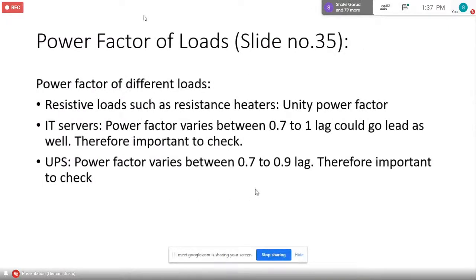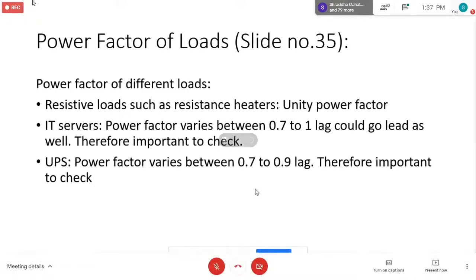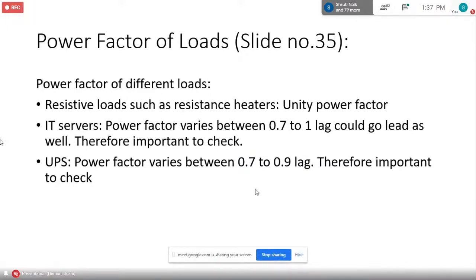Power factor of loads. So the loads determine the power factor of that system for the installation. The different loads: resistive loads such as resistance heaters have unity power factor. IT servers' power factor varies between 0.7 to 1 lag, could go lead as well. Therefore it is important to check.